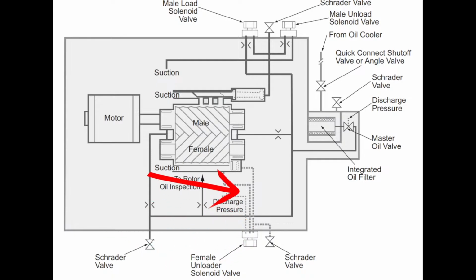So the female unloader is controlling this internal check assembly to the compressor. That is my understanding of what this is doing internally, where these are rediverting, say, oil to push the slide back and forth. The female unloader is actually triggering a type of gate, the way I understand it, internally. And yes, it does function just like a hot gas bypass. It's just internal to the compressor. All of this is inside of there. It is not external. And yes, when the solenoid is de-energized, then this will bypass. And what that means is that it will allow this little gate in here to open, and the discharge gas will flow back into the suction.